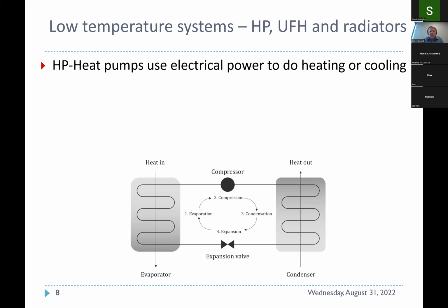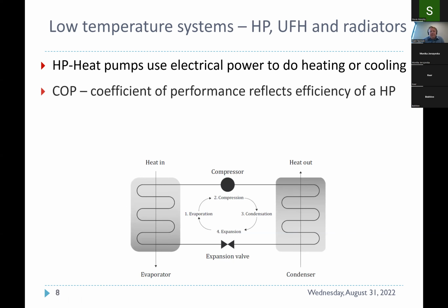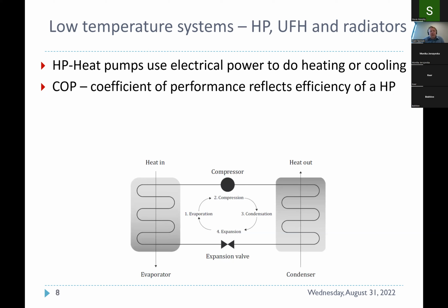So you'll see a lot of the older type that have a radiator at the back of it. You'll see that covered in dust and cobwebs at the back. You feel the heat coming off that. So heat pumps in heating mode are measured by their coefficient of performance at a specific outdoor temperature and flow temperature. It is very important when you're being given a COP on a heat pump to know at what conditions that is being given.